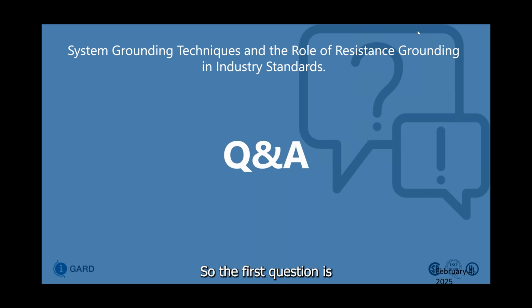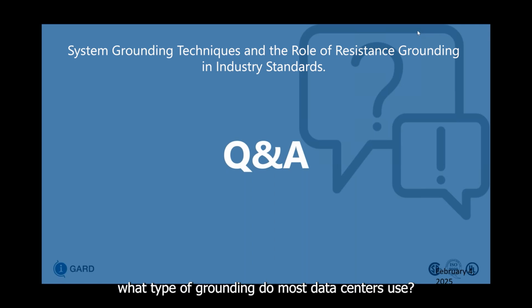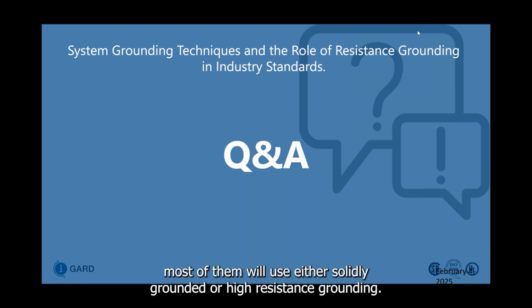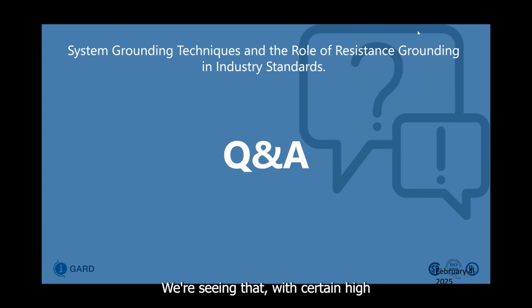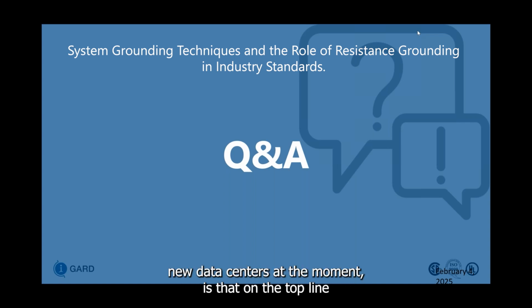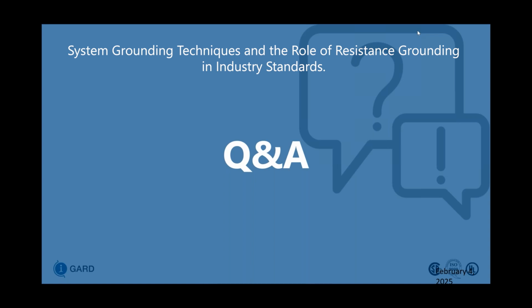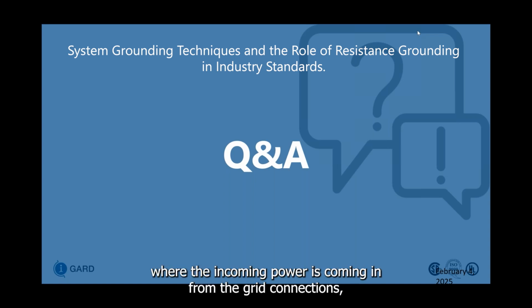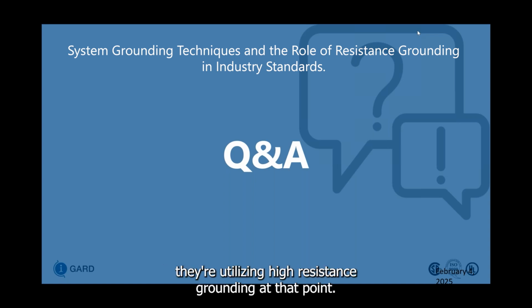So the first question is, what type of grounding do most data centers use? On the higher end of data centers, most of them will use either solidly grounded or high resistance grounding. We're seeing that with certain high level companies that are building new data centers at the moment, on the top line, where the incoming power is coming in from the grid connections, they're utilizing high resistance grounding at that point.